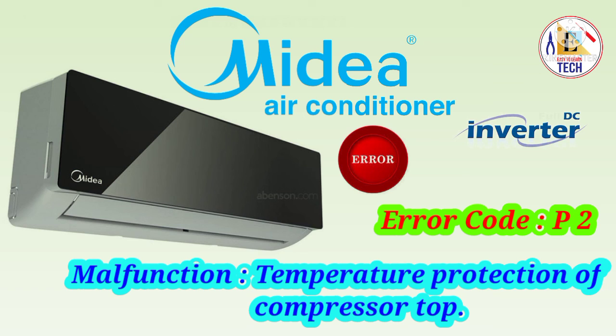You have to check the connection of that sensor, if it is connected properly in your outdoor PCB or not. If it is not connected, connect it properly and place it properly. Then you have to start the unit again, and again if you are getting the same error, you have to change that sensor and you will get the solution for the error P2.